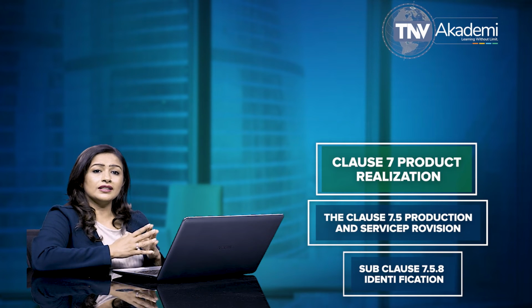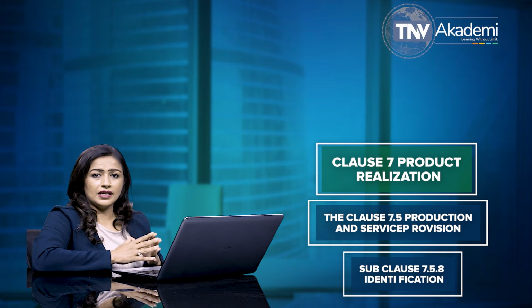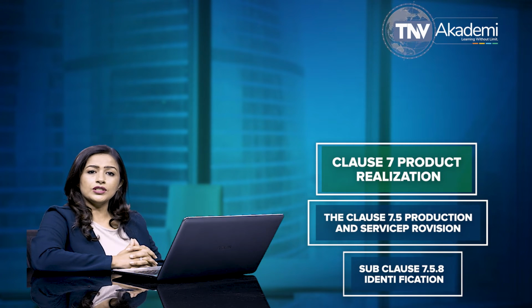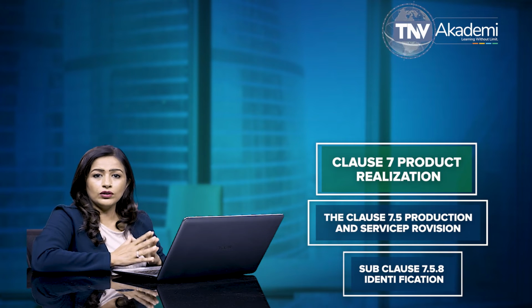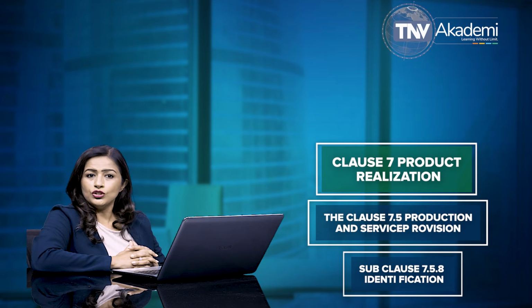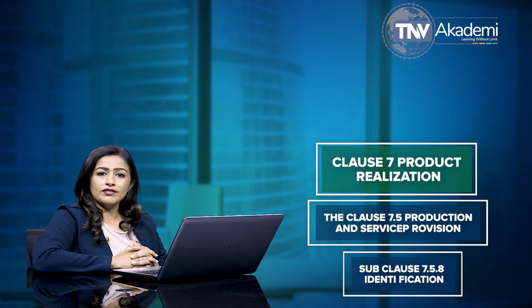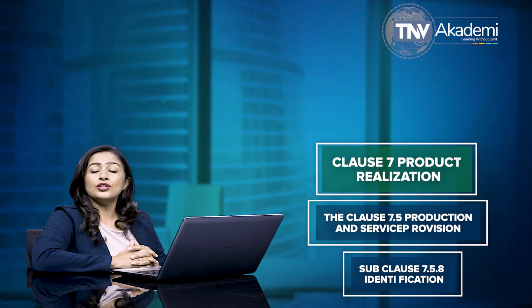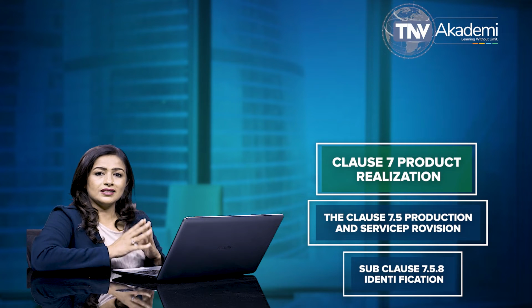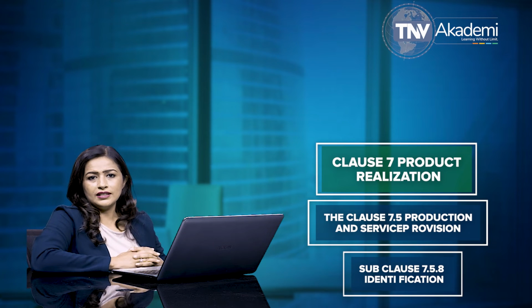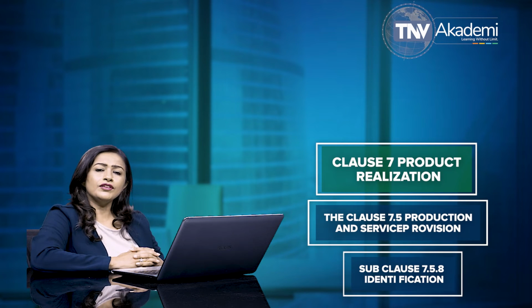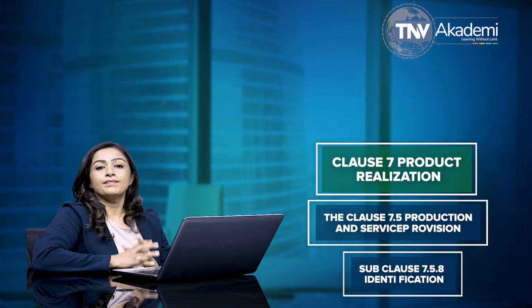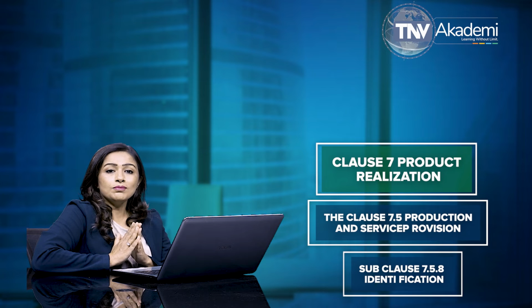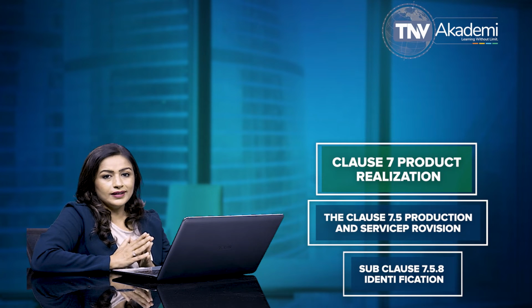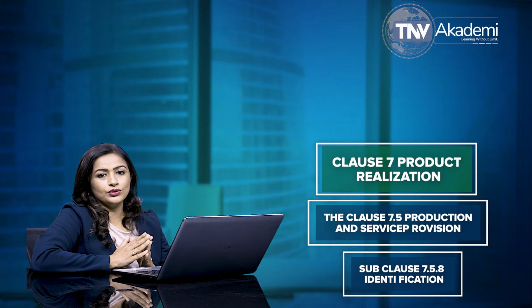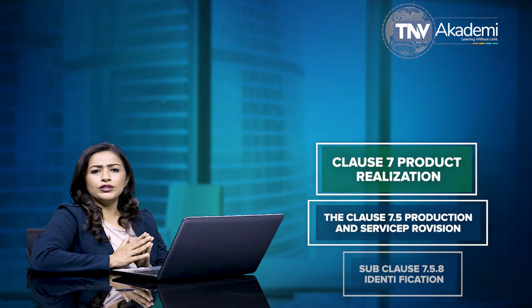that only product that has passed the required inspections and tests is dispatched, used, or installed. This also includes ensuring the product is released under an authorized concession. Subclause 7.5.8 further states that the organization is required to document a system to assign unique device identification to the medical device, if required by applicable regulatory requirements. As per this clause, the organization must document procedures to ensure that medical devices returned to the organization are identified and distinguished from conforming product.